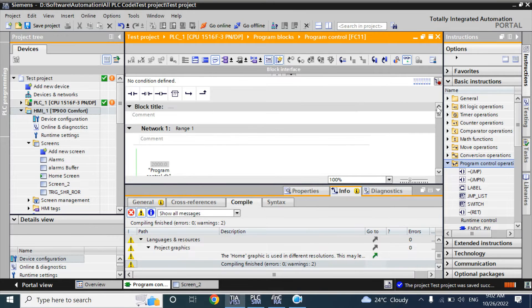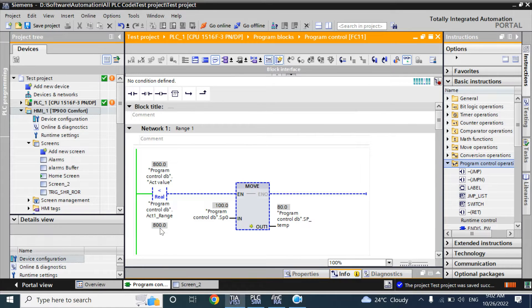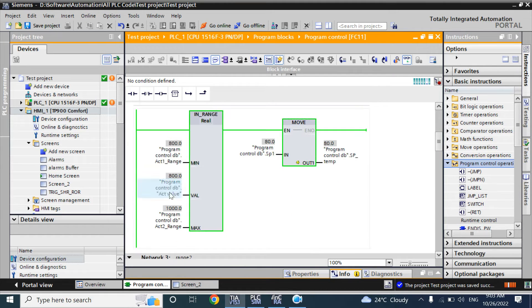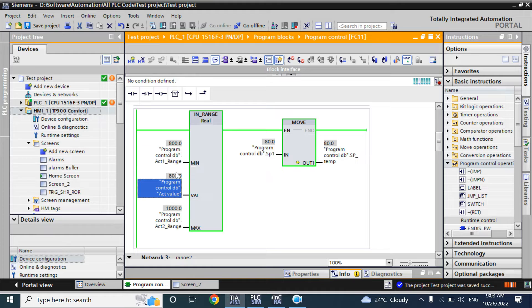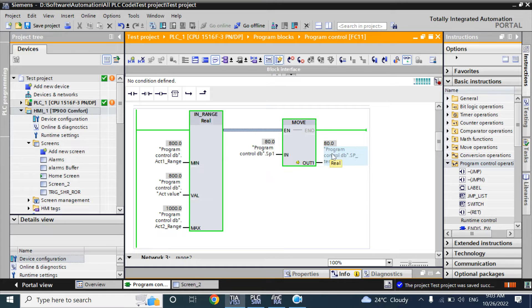Here we have made the logic: if the actual value from the field is less than Actual Range 1, it will take SP0 setpoint to the SP Temporary. If the actual value from the field is in between Actual Range 1 and Actual Range 2, it will take SP1 to SP Temporary. When the value is in that range, the In-Range output will be high.